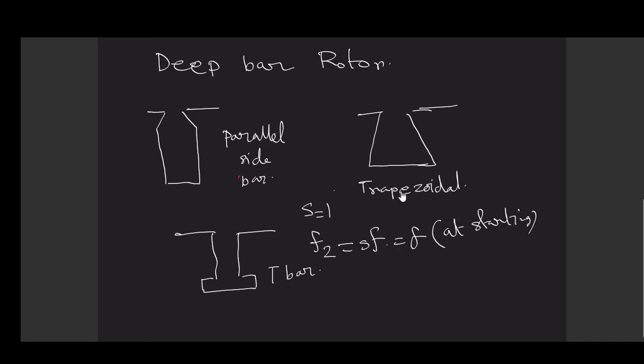Well, before I proceed, one thing I just want to mention: this T bar has a mechanical advantage because you can understand the way it is holding the conductors. Conductors are filled here. Now you can see that a part of the conductors is solidly embedded inside this groove. So it gives us the most mechanical strength. So this is a mechanically advantageous design.